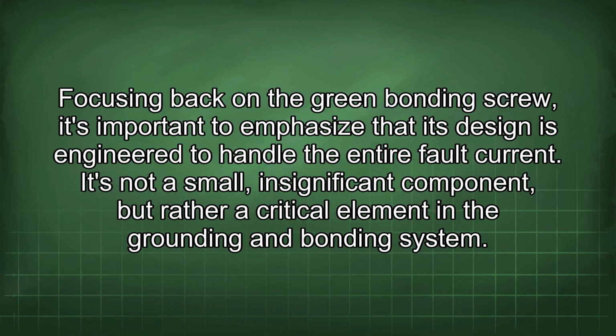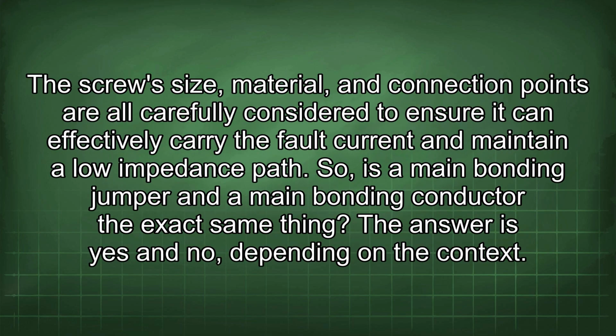Focusing back on the green bonding screw, it's important to emphasize that its design is engineered to handle the entire fault current. It's not a small, insignificant component, but rather a critical element in the grounding and bonding system. The screw size, material, and connection points are all carefully considered to ensure it can effectively carry the fault current and maintain a low impedance path.